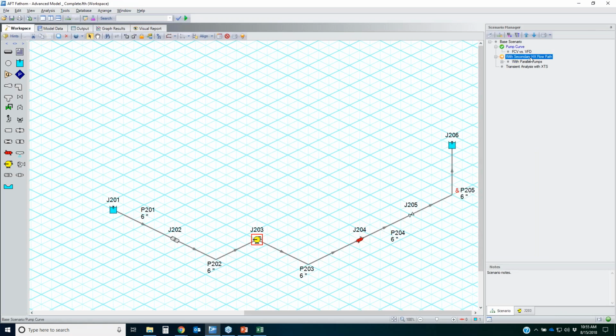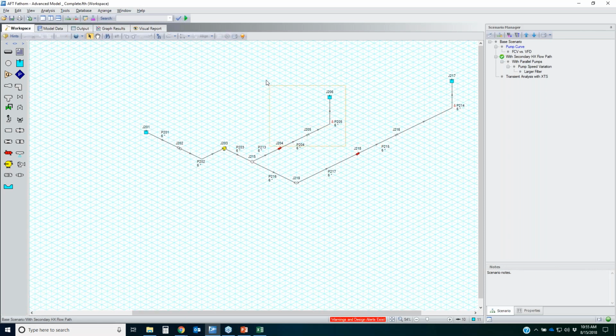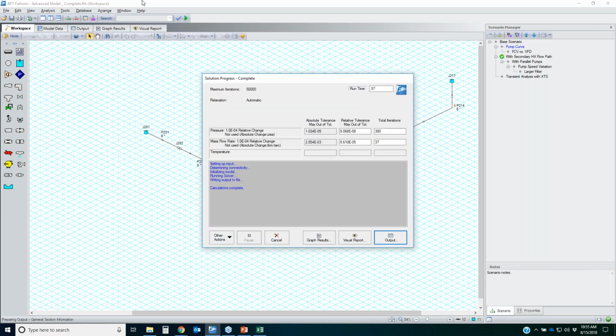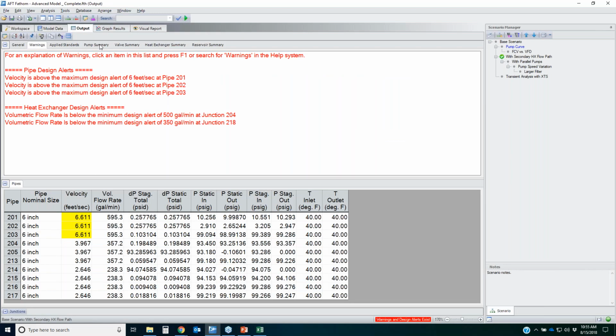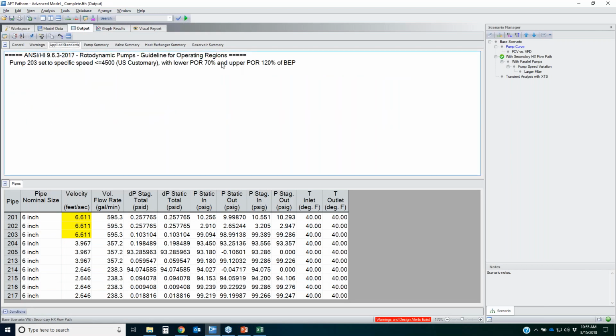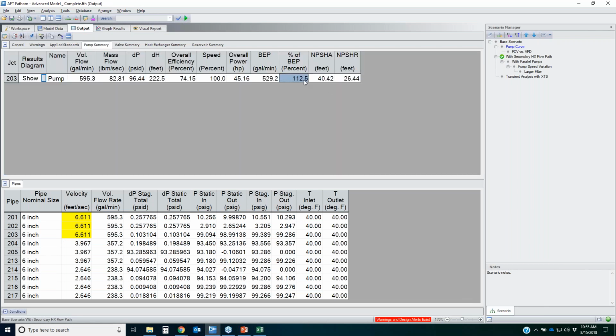It's doing a phenomenal job. I have another scenario where I later had an expansion. So basically, I took this system right here and I duplicated it and I modified it slightly. So this is a whole individual portion of the system. So now, when I run my original pump with this new system, the flow rate is going to be different. So based upon my new flow rates here, if I go to my applied standards, this is my operating range there. I'm operating at 112% of the BEP. So I'm still not outside that window, but you can see your flow is higher, 595 gallons per minute.